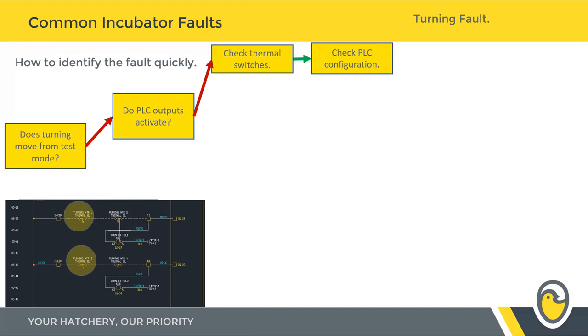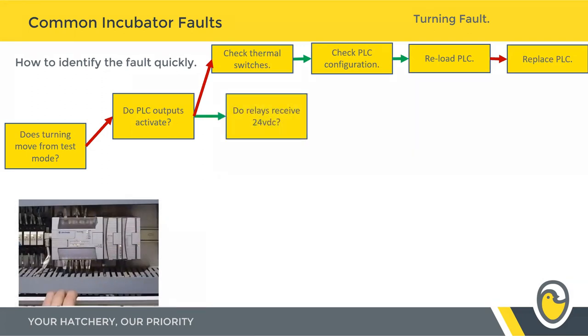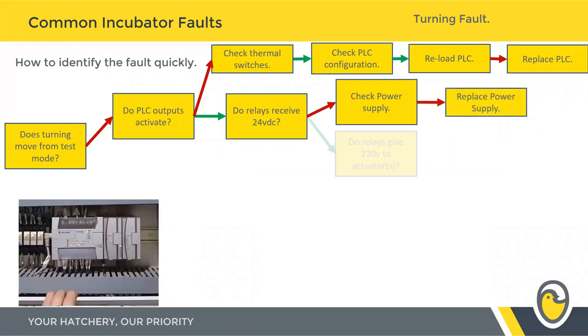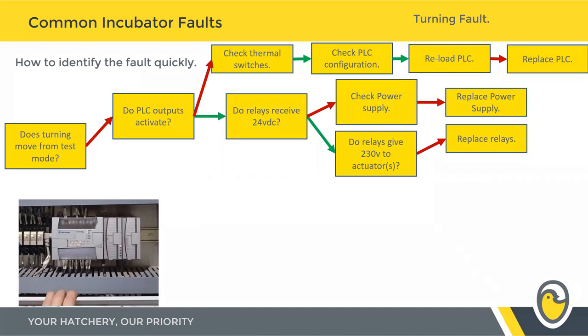If the thermal switches are good, check the PLC configuration to ensure nobody has accidentally changed a setting. If the configuration is correct, reload the PLC, then replace the PLC as an absolute last resort. If PLC outputs do activate, check whether they're activating the relays — is the relay receiving 24 volts? If not, check and replace the power supply. If it does receive 24 volts, does the relay then give 230 volts, or 24 volts for pneumatic actuators, out to the actuators? If not, replace the relays. If it does, you're down to replacing either the turning actuator or the solenoid in the case of the bottom pneumatic turning system.